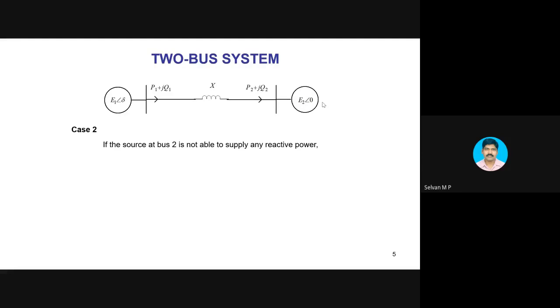We'll assume it is a PV system connected to the grid, or it is an induction machine connected to the grid, which cannot supply reactive power. Right? Okay, in that case, what happens? We will see. Since it is not able to supply any reactive power, I am mentioning that Q2 equal to zero, because I don't have any other loads. So definitely Q2 is zero. It is not supplying any. When I substitute this Q2 equal to zero and solve for E2, the voltage becomes 0.866 per unit. Bus 2 voltage drops down, right?